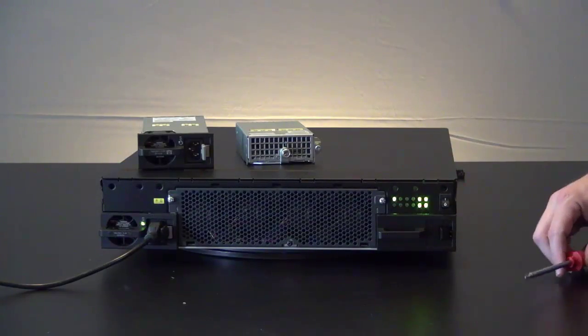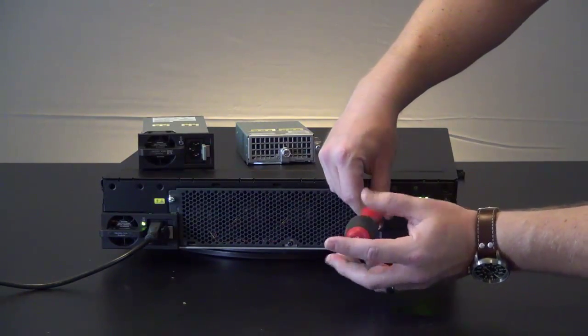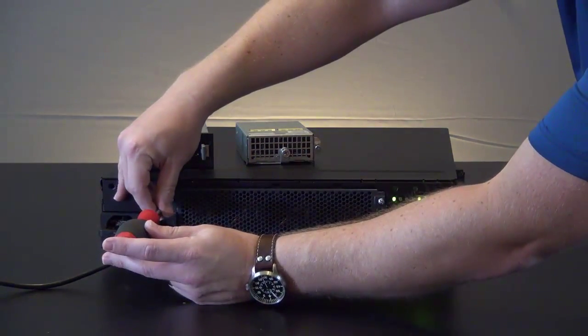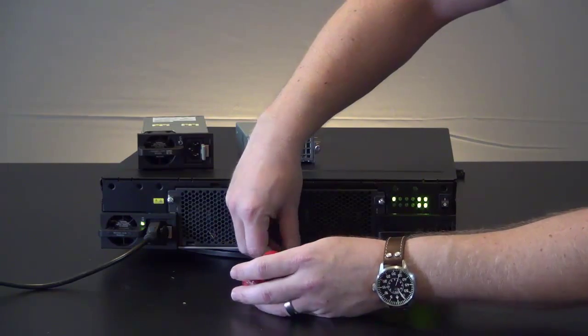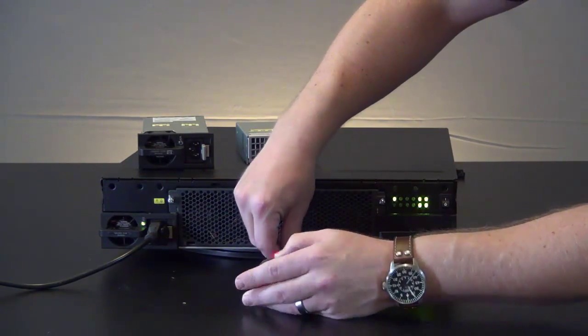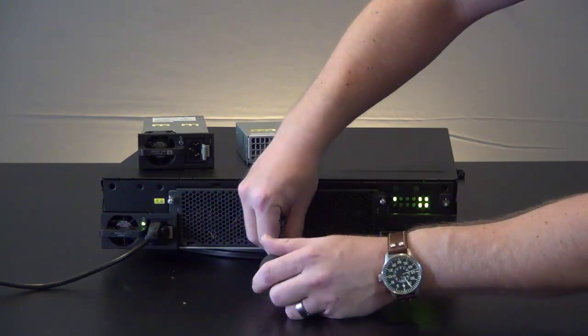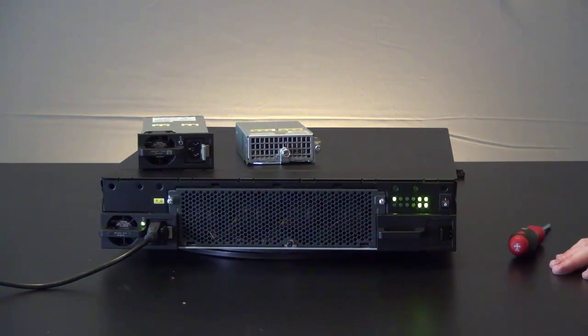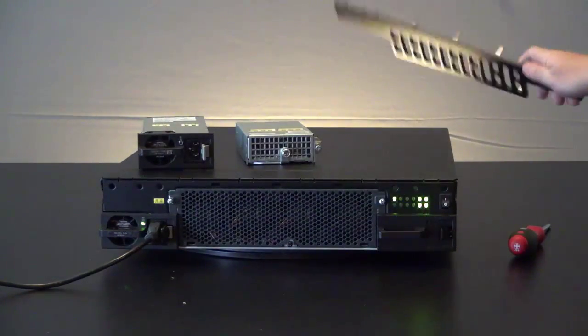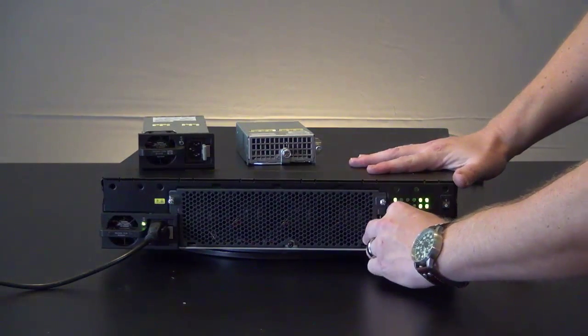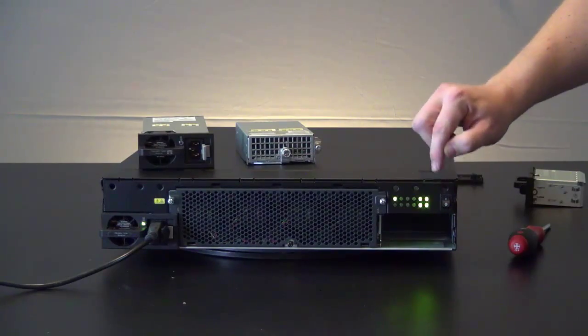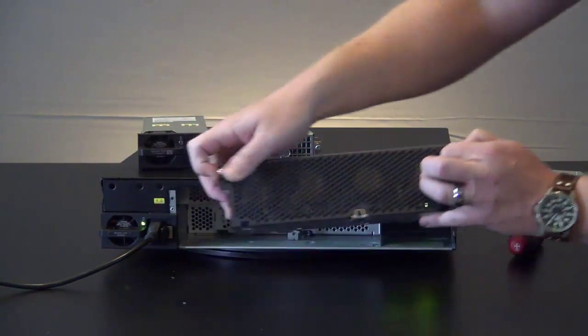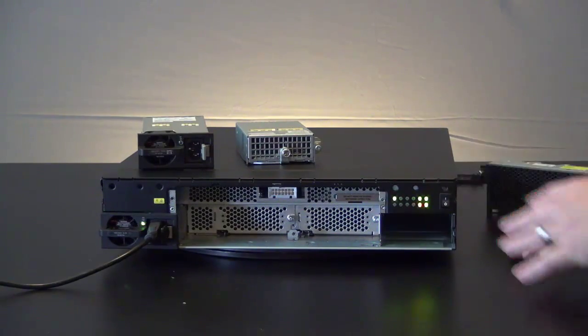So, to get inside of the fan tray, all you have to do here is just remove three screws. They're actually captive screws, so you just have to loosen them. One on either side of the fan tray here, and then one in the lower middle. This is a black screw. It's actually painted black for a reason. That's because this is the only screw that's visible outside of the bezel. And some of the early versions of this guy, you can actually see that silver screw through the bezel. So, we painted it black so that you can't really see it through there. Okay, so we're ready to remove the fan tray. I'm going to go ahead and remove this blank for the new power supply just so that it's not in our way. Be very careful about this power switch and just pull the fan tray right on out. Things get a lot quieter. You can see the system is flashing a nice warning light. It is not happy with us right now, but it is still up and running.